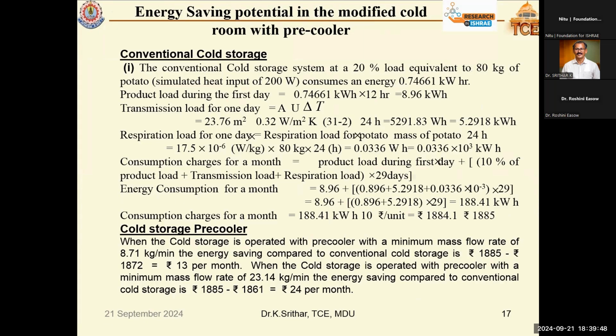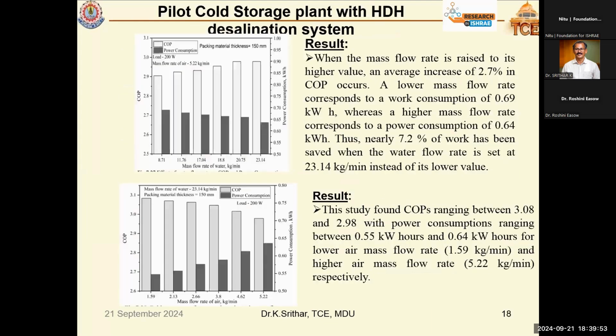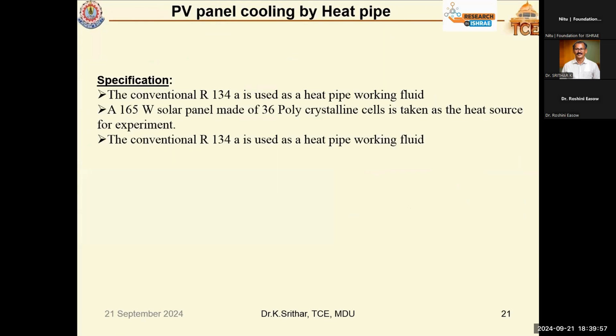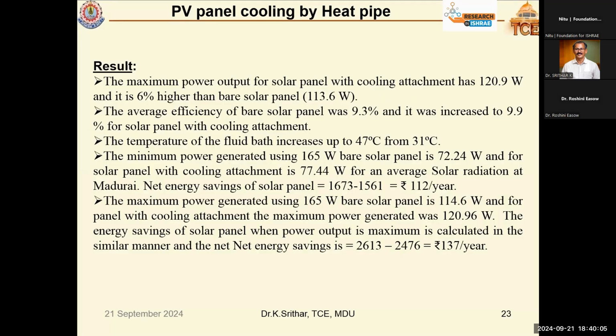For that, we are using a small test PV panel of 165 watt capacity, and R134a as the working fluid. The outcome of the results: number 1, we are having an increase in panel power production. The conventional panel produces only 113.6 watt, whereas our alternate arrangement gives a power production of 120.9 for this small panel. And also we have continuous hot water with a temperature rise from 31 to 47 degrees. Initially the electrical efficiency is 9.3%, now it has increased to 9.9%. So that is the first advantage.